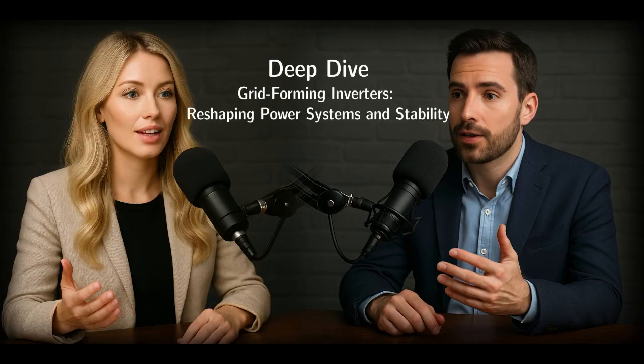Okay, which brings us squarely to the revolution. Grid-forming inverters. If the old way was following, what's the fundamental change here? This is the game changer. Grid-forming inverters operate as controlled voltage sources. This is the key difference. They can independently establish and maintain the grid's voltage and frequency. They don't need an external reference waveform to follow. They create it. They build the grid themselves, locally at least.